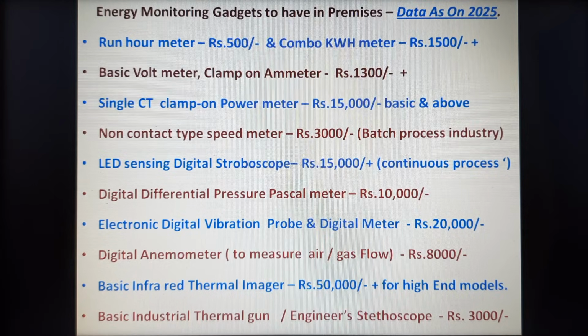This is becoming mandatory for many of the MSME segment now. This infrared thermal imager costs 50,000 at a basic price, but it goes to almost 10 lakhs also, depending on your requirement and the criticality of your application. With thermal imaging of all your motors, machines, the EB power boards and all your motor panels, and the process temperature gradient, everything can be monitored, and you can detect the hotspots in the process.